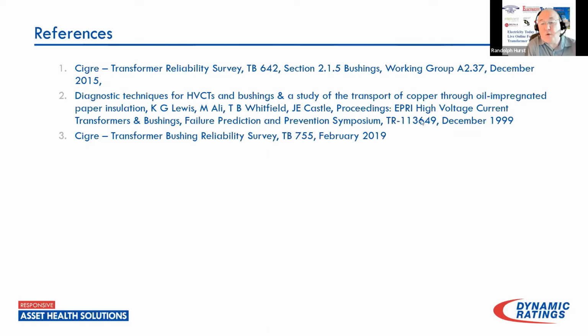Okay. Next question. How accurate and reliable is the frequency sweep test for C1 and C2 power factor? Should one replace the bushings if C1 and C2 readings are out of threshold limits at frequencies other than 60 hertz? The answer to that is the sweep frequency response analysis. This is an offline test, for those that don't know. It is far more sensitive and gives a lot more detailed information about the moisture condition not only inside the bushing, but also inside the transformer when you do the test.